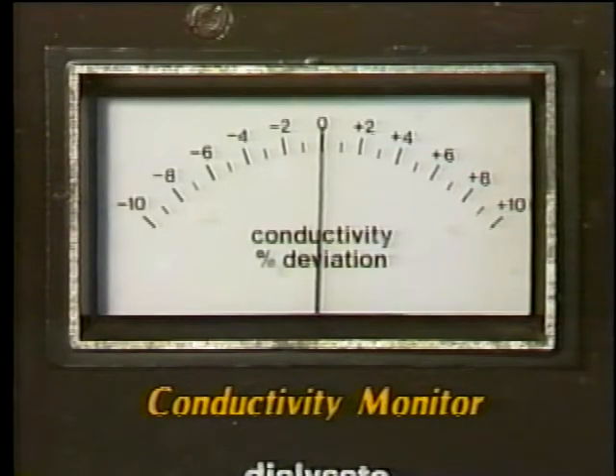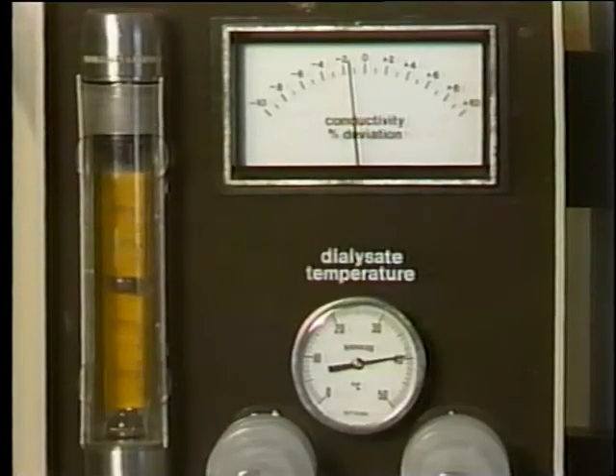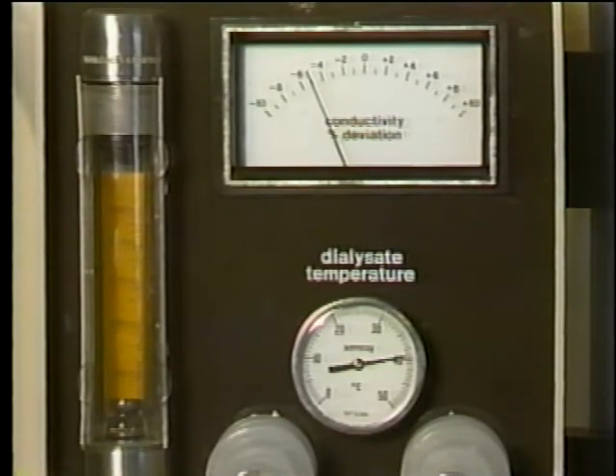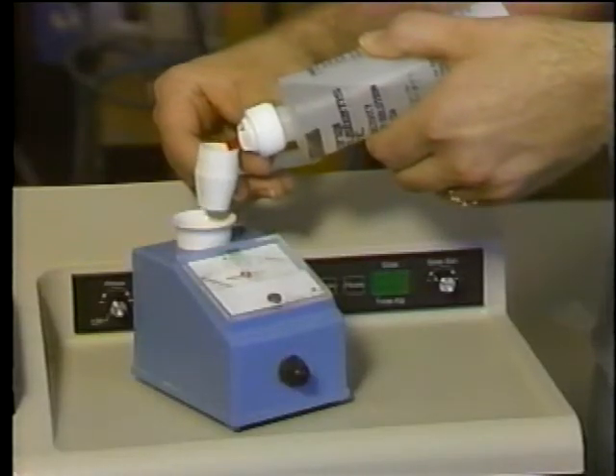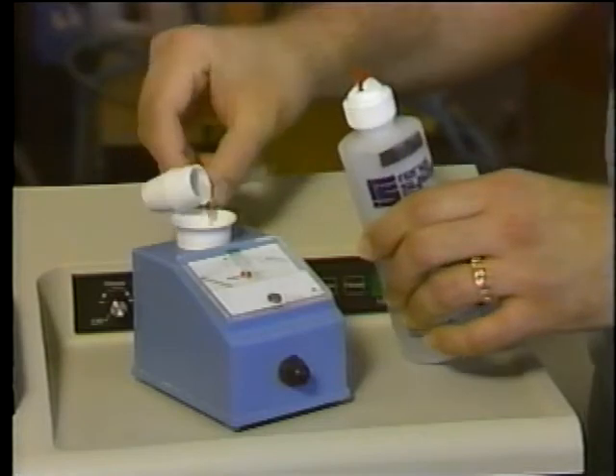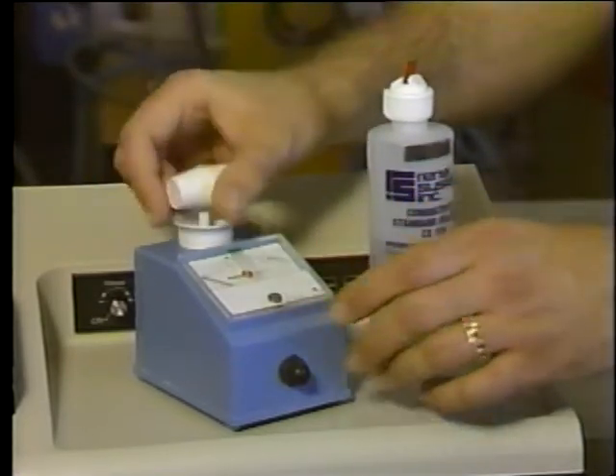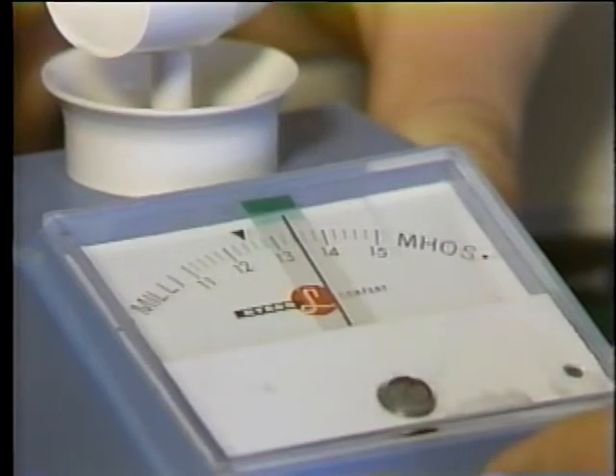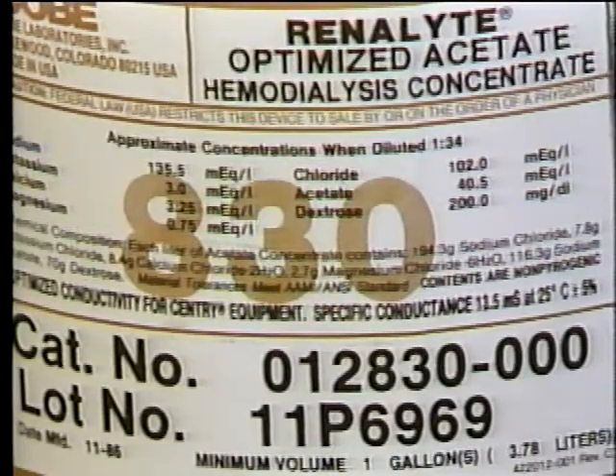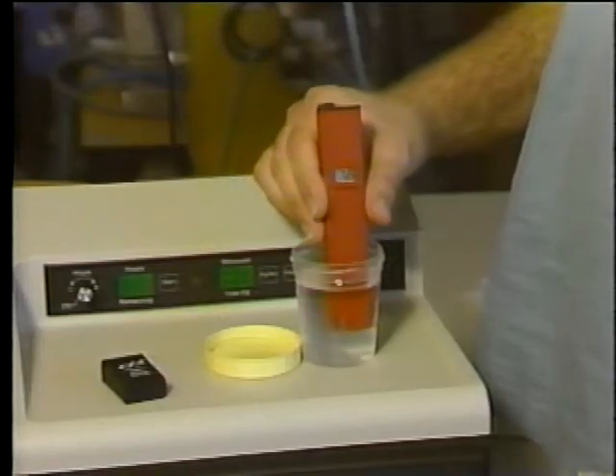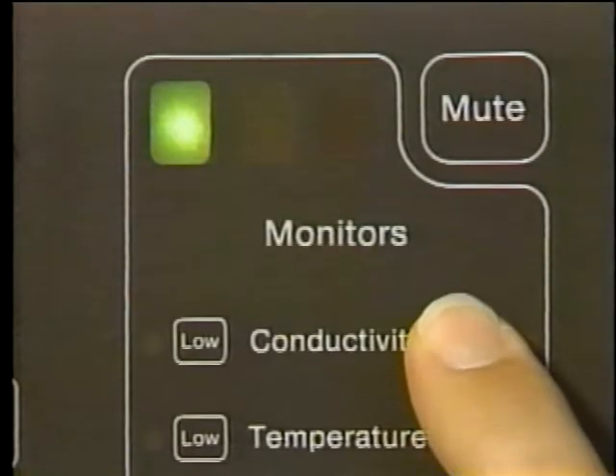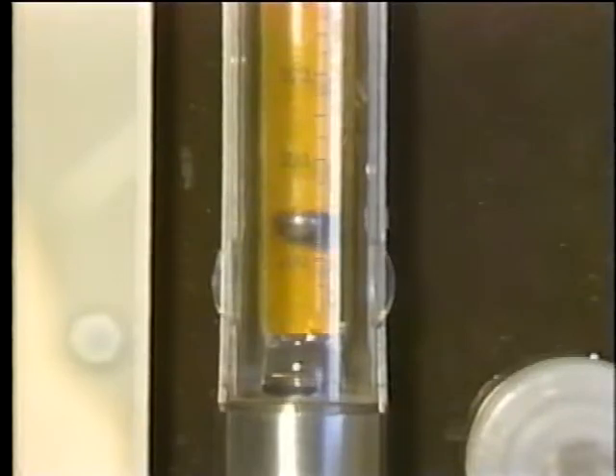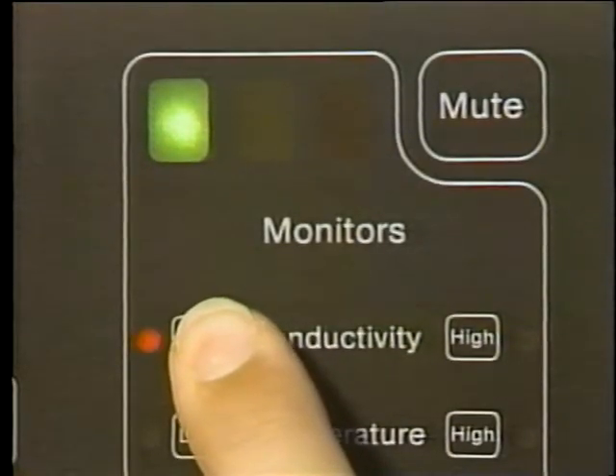Another critical safety feature on the dialysis machine is the conductivity monitor. To prevent electrolyte imbalance or hemolysis, it's imperative to know that the dialysate composition is correct and that the conductivity monitor alarm is functioning. The dialysate should be independently checked with a conductivity meter, which is calibrated against a standard reference solution. You should know the correct conductivity meter reading for the concentrate being used. For bicarbonate dialysate, an independent pH check must also be done to assure proper electrolyte balance. Once you know that the dialysate is correct, check both the high and low conductivity alarms. Verify the bypass function as well as the audible and visual alarm.